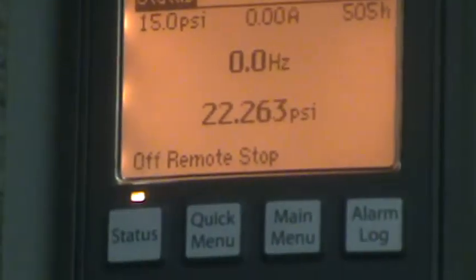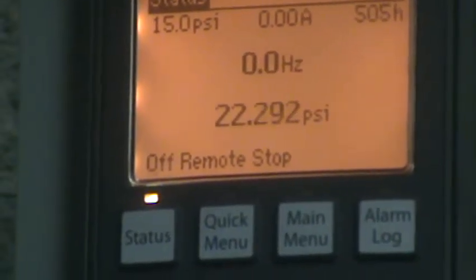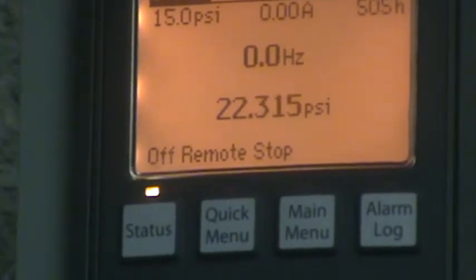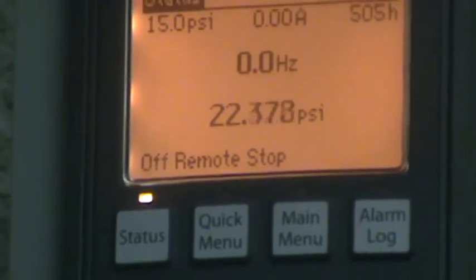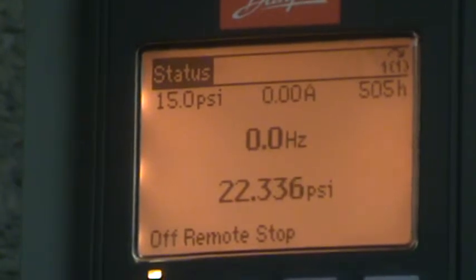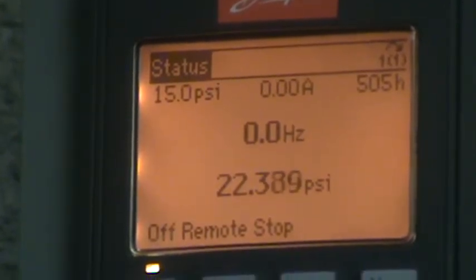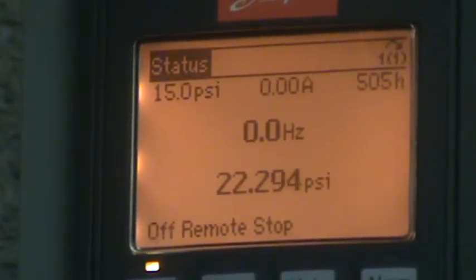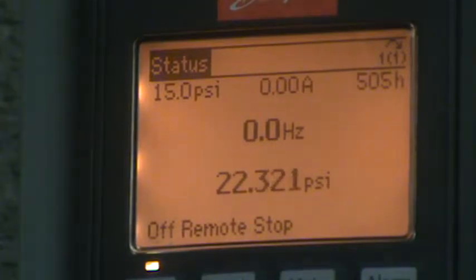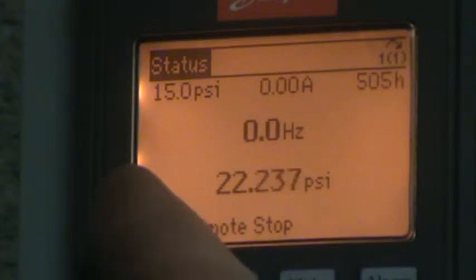Depending on what the warning is, it'll stay in that state, sometimes indefinitely, or sometimes for a time period. Most electrical things are time period. If you're at a high current, it'll stay at that high current for a while, and then the drive will say, you know what, this is enough. It'll go into an alarm and it'll shut down, because it doesn't want to damage itself, and it doesn't want to damage the motor. Is the alarm audible? No, it's just a blinky light. Blinky red light here, it'll go from warning high current to alarm high current.